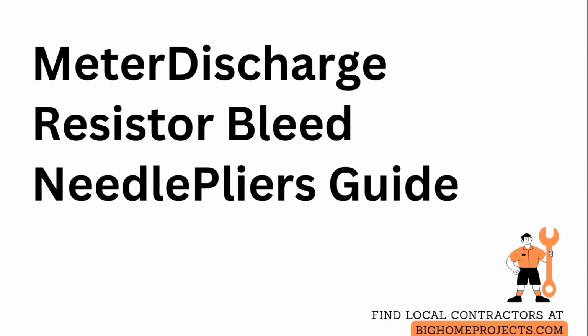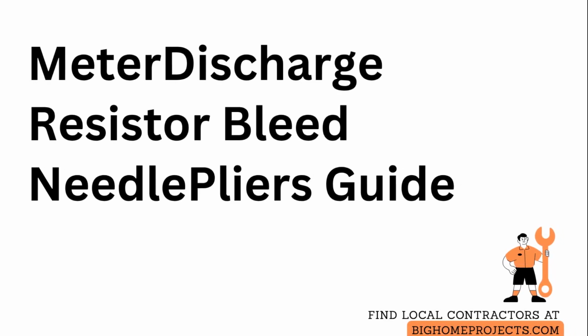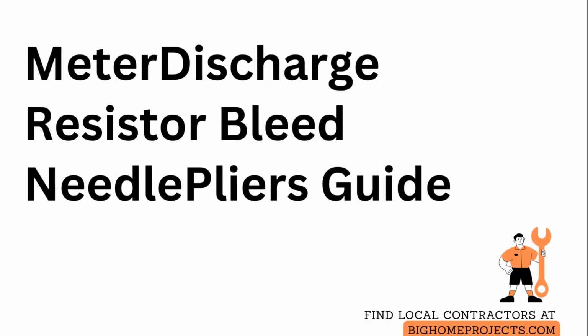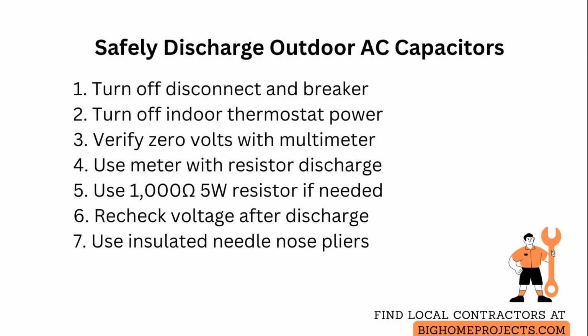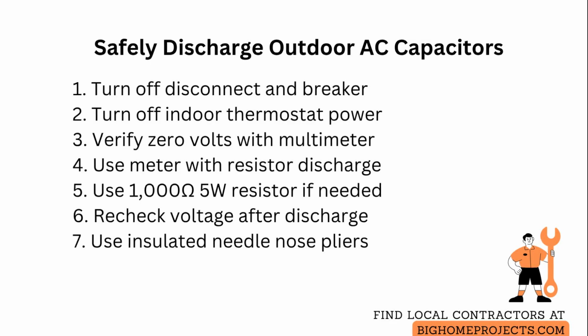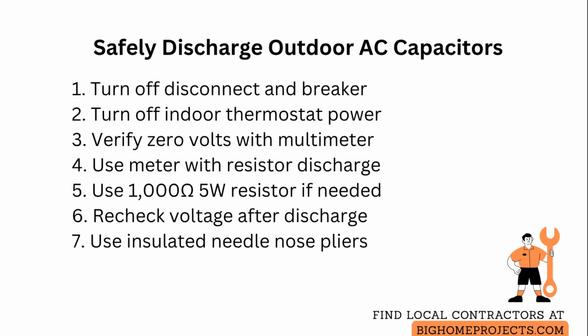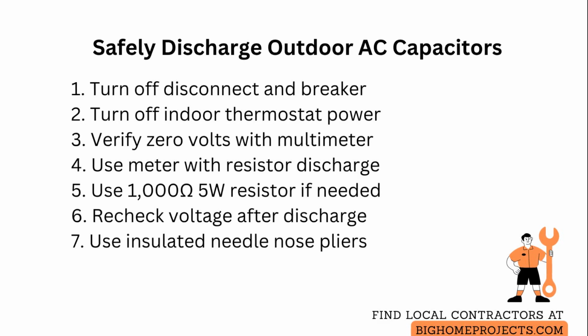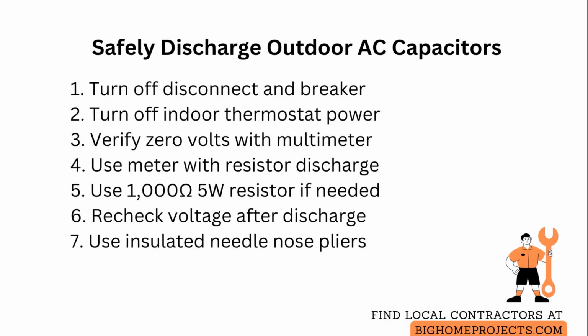Always confirm the outdoor air conditioning capacitor is fully discharged before touching any terminals. Start by switching off the outdoor unit at the dedicated disconnect, and then turn off the indoor thermostat and circuit breaker to remove all power sources. Use a digital multimeter set to the highest voltage range and probe the capacitor terminals to verify there is no residual charge. Readouts above 0 mean it still holds energy.